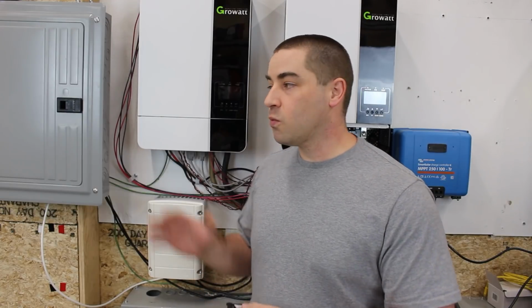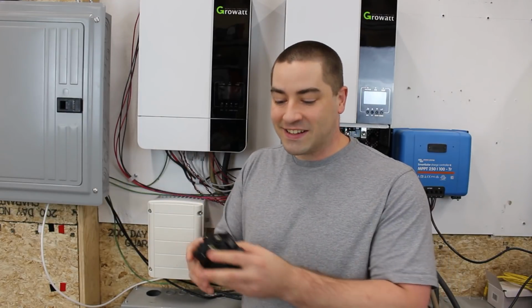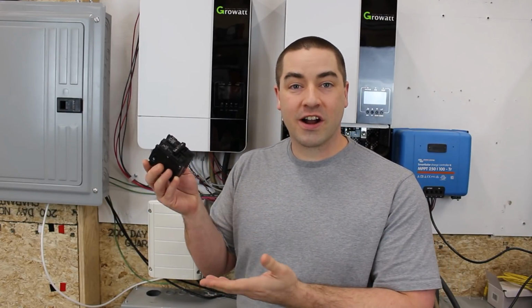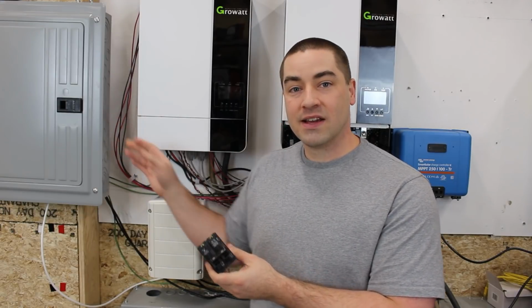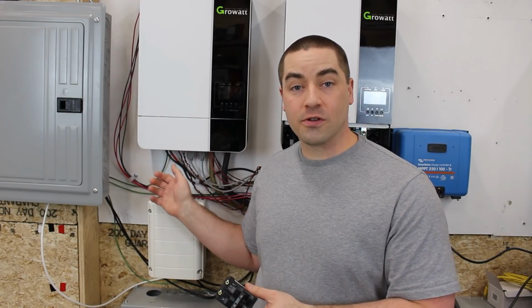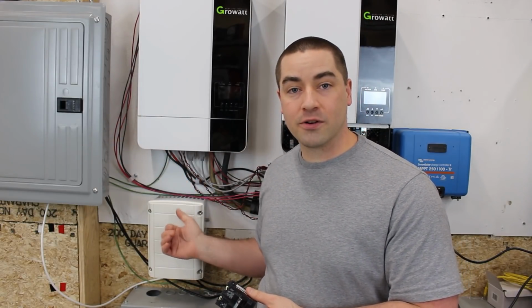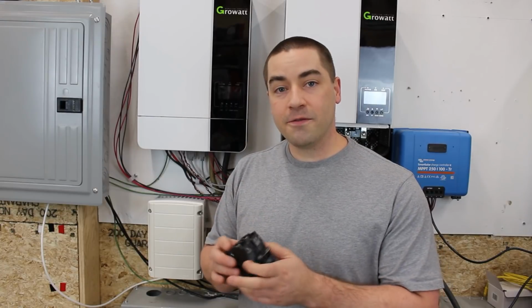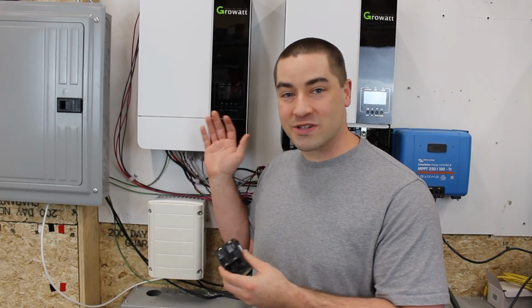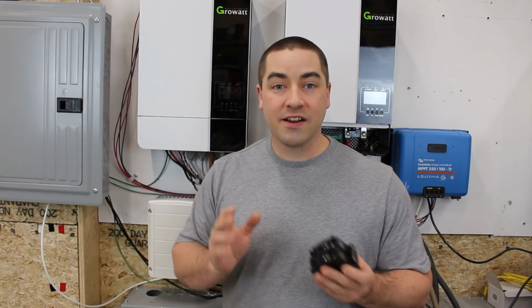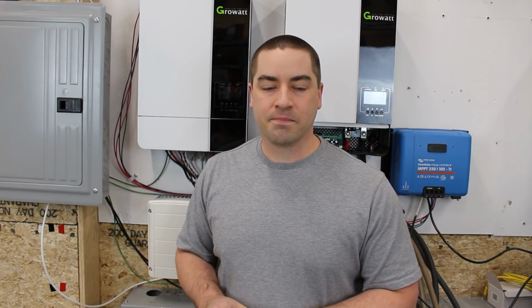But there were lots of viewers who rightfully so had a concern that what if, for whatever reason, this circuit breaker shut off inside this box, we would lose the neutral because we'd no longer be supplying power to the auto transformer. Now if that happened and these inverters were still supplying power, then there is the potential that we could fry some electronics. So certainly we'd want to eliminate that as a possibility.